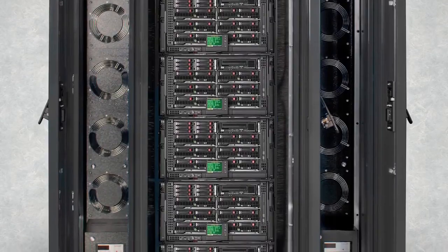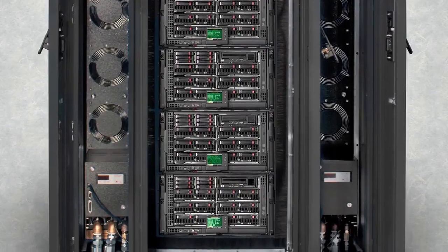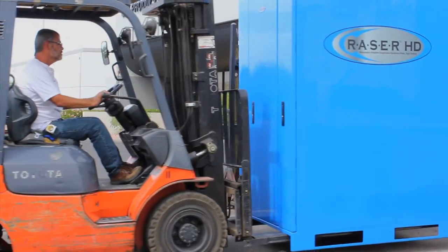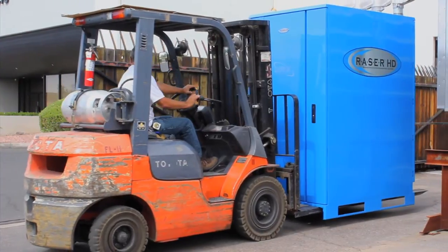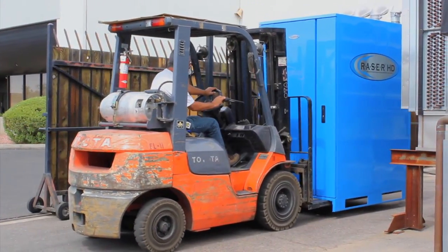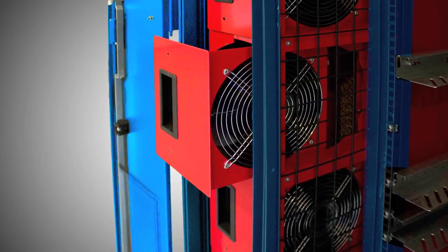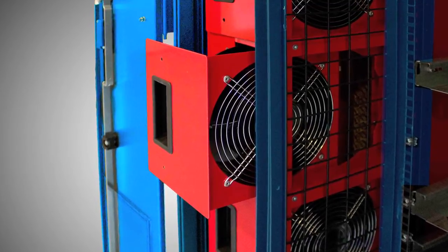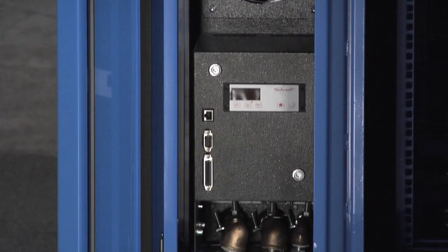The Raser HD includes 19-inch vendor agnostic racks that accommodate the world's most advanced IT equipment, optional blue or black powder coating, a relocatable platform that can be easily moved with a pallet jack or forklift, and shock and vibration isolation allowing the cabinet to be built fully populated with IT equipment and shipped directly from the supplier to the data center. Additionally, the Raser HD has several unique features including hot swappable and field upgradable heat exchanger units that support multiple configurations while adding redundancy and onboard monitoring for air temperature, flow, water temperature, leakage, humidity, and fan speed — all environmental elements associated with the operation of the unit.